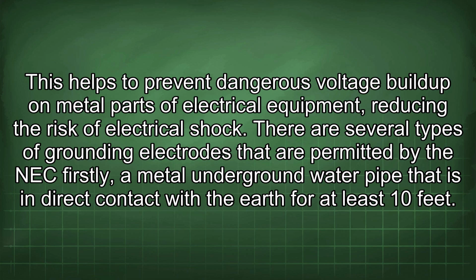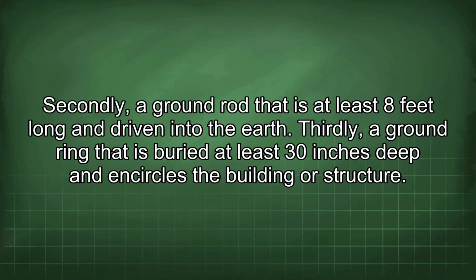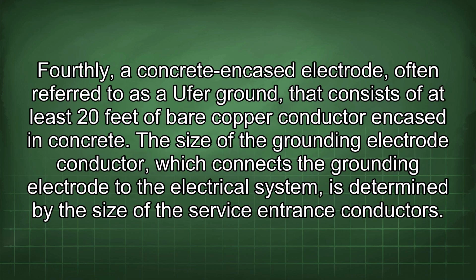There are several types of grounding electrodes that are permitted by the NEC. Firstly, a metal underground water pipe that is in direct contact with the earth for at least 10 feet. Secondly, a ground rod that is at least 8 feet long and driven into the earth. Thirdly, a ground ring that is buried at least 30 inches deep and encircles the building or structure. Fourthly, a concrete-encased electrode, often referred to as a Ufer ground, that consists of at least 20 feet of bare copper conductor encased in concrete.